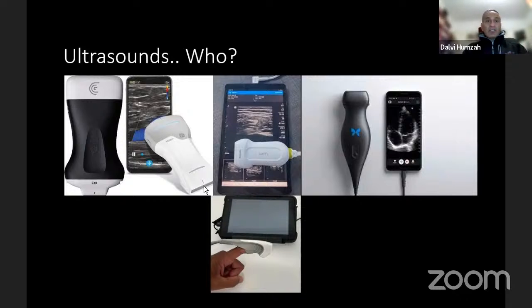It has a linear transducer, which we tend to use mostly for aesthetic use. And there is a curvilinear transducer on the other end, which we use for deeper ultrasound, such as abdomen and breast. So in my practice as a surgeon, I can use it both for superficial work around the face, or if I'm looking deeper in the abdomen, breast implants. This is quite a useful one too. So, the frequency here is about 12 megahertz, and the curvilinear runs at 8 megahertz.